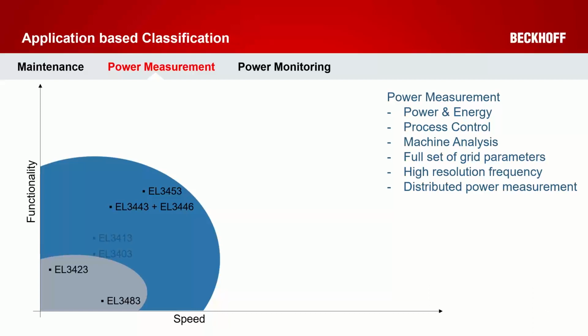A full set of RMS grid parameters, including harmonics, is supported and calculated internally by the terminals themselves. As an add-on, we have a high-resolution frequency measurement to measure and evaluate the grid stability. The keyword in the background is the virtual inertia evaluation. As another add-on, we have a distributed power measurement system, with one voltage and multiple current measurement points, realized with one EL3443 and multiple EL3446. I will explain this later in my application slides.